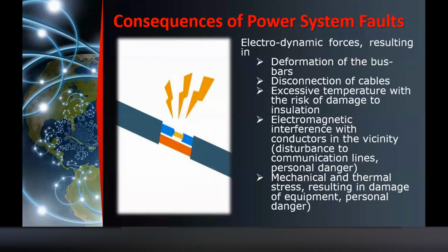Pumipitik. In reality, merong mga nangyayaring ganyan pag gumagawa ng live works, no? Minsan nalalaglagan ng tornilyo yung bus bar, no? Sa sobrang lakas ng fault, single line to ground fault, nadi-disconnect yung mga kable dun sa mga connector. So never ever do a live work na walang kasanayan, or much better na shutdown na lang yung system. Okay? Number 3, excessive temperature with the risk of damage to insulation. Ano yan? Pwede nating sabihin yan, or excessive temperature with regards to the fault current is arc flash. So meron kang excessive heat.